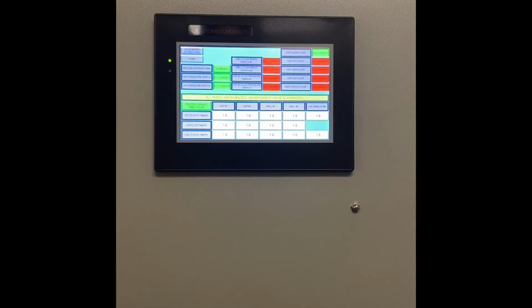And there's a lot of data here, but it's really pretty straightforward. The top half of the screen are all of the discrete inputs, with the exception of the groundwater storage tank in service bit. We'll get to that in a second. So the lead pressure switch, lag pressure switch, the flow pressure switches in the middle, and the float switches on the right all have a green or red button next to them that either says green, normally open contact, or red, normally closed contact.